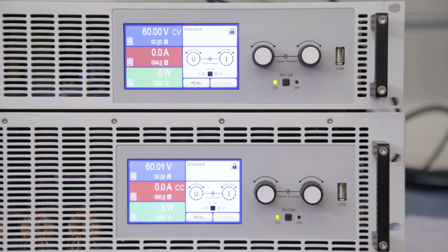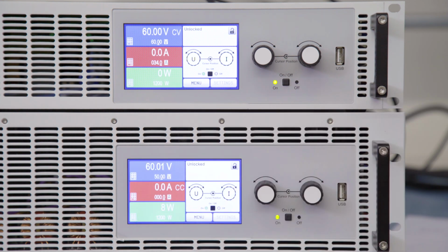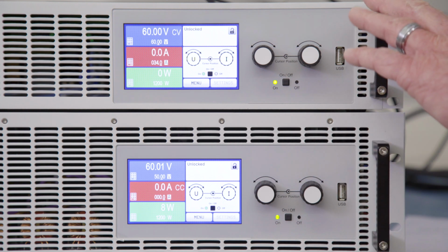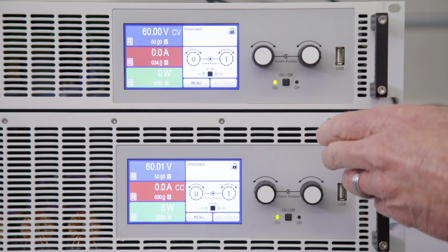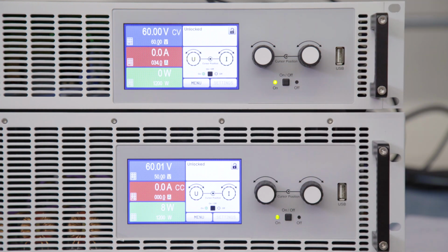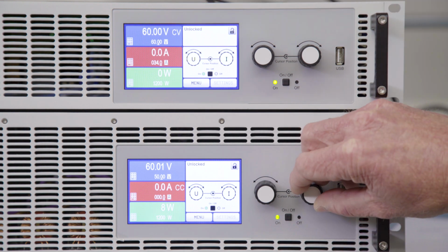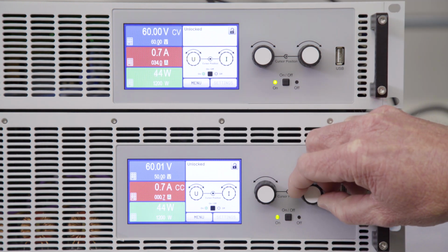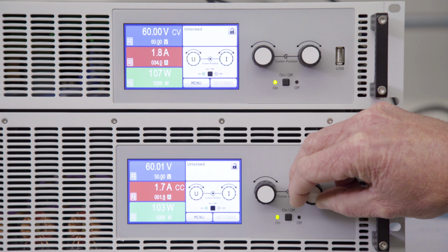The third mode of operation that we're going to show you here is what's called constant power mode. In constant power mode, once the programmable power supply reaches its programmed constant power limit, the power supply will fluctuate the voltage based on the current draw that's programmed to be able to maintain a constant power output. What you can see here, we set up 60 volts, just an arbitrary 34 amps of current. As I start to increase the current on the load, you'll notice the current on the power supply starts to increase while the voltage is still maintaining in constant voltage mode.